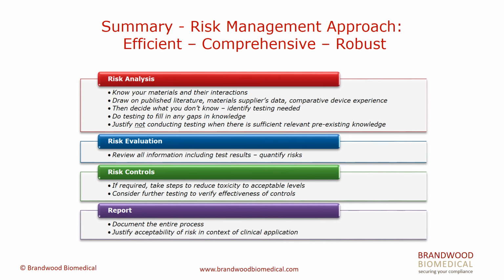So in summary, this risk management approach to biological evaluation is essentially efficient, it's comprehensive, and it's robust. It begins with a risk analysis of understanding the materials and the interactions, drawing on the published literature, material supplier data, comparative device experience, and deciding what you don't know. What testing do you need to add? You do the testing to fill in any gaps in the knowledge, and you can justify not conducting testing where there is sufficient relevant pre-existing knowledge.